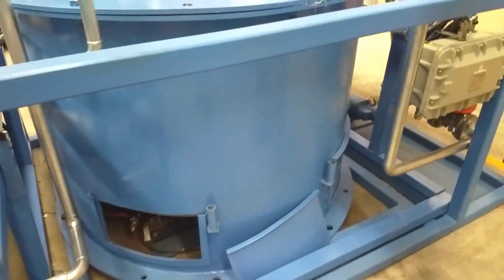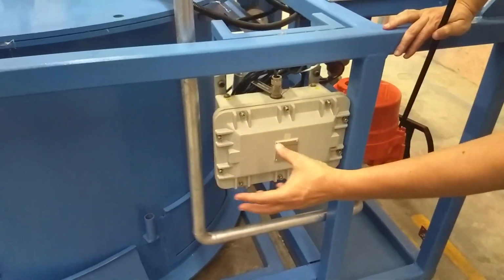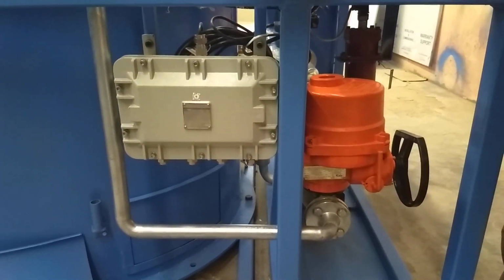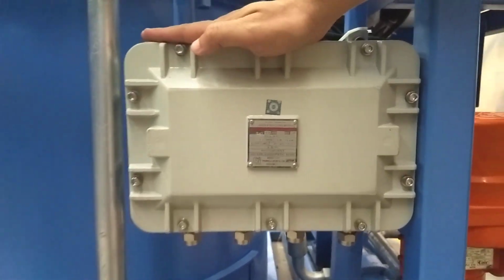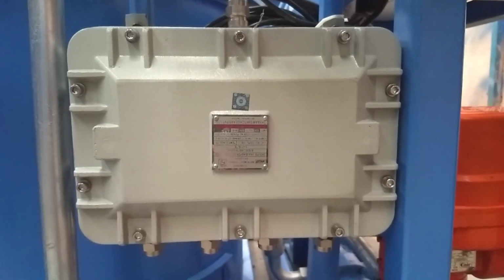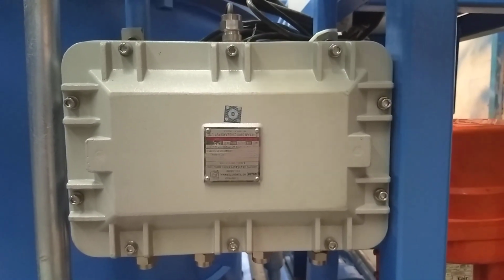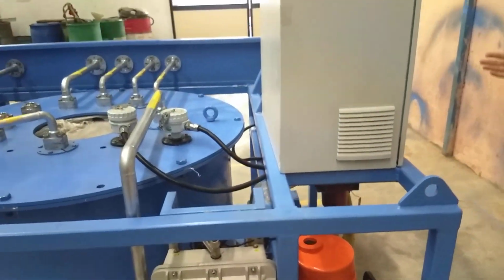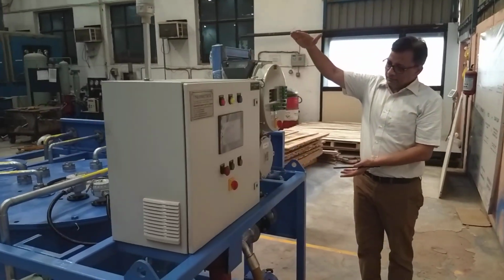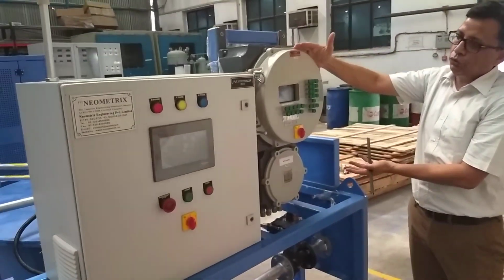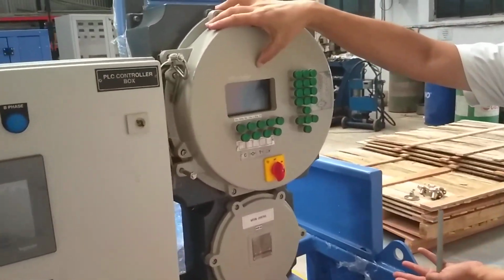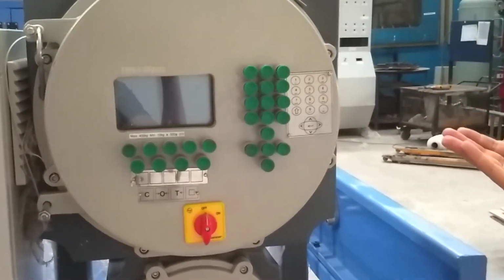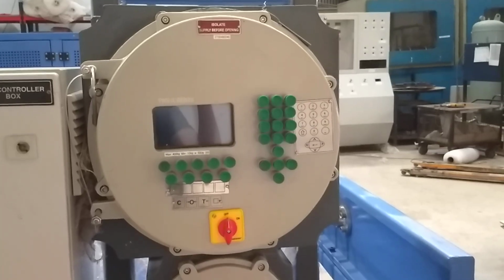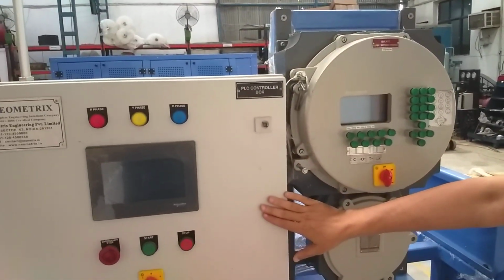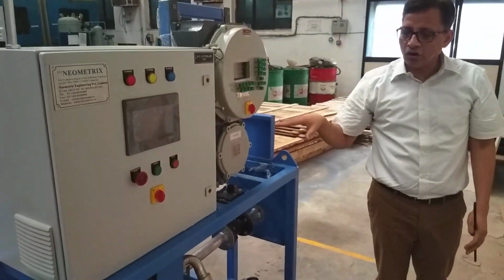Now I will explain various other parameters of this system. We were talking about the load cells. Now there are 4 load cells. All those 4 load cell wires come to this junction box provided by Mettler Toledo USA, and all the load cells are terminated here. From this junction box the cable goes to the Mettler Toledo explosion proof tank weighing digital panel, and this is the TWS L series tank weighing system L series panel, which is monitoring the load being measured by the 4 load cells, and it is communicating to this PLC controller on RS channel in a digital manner.